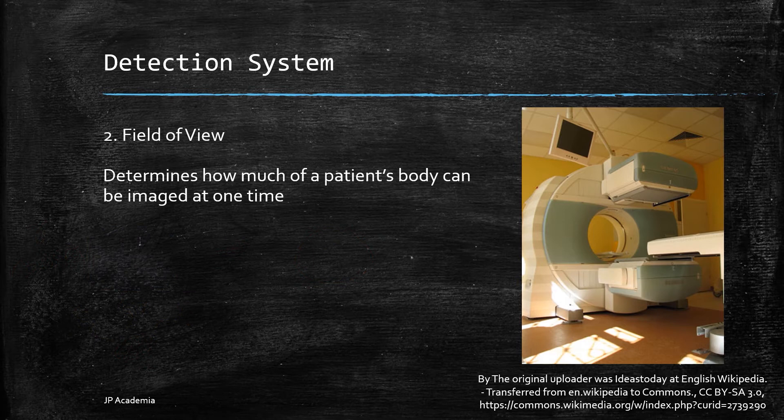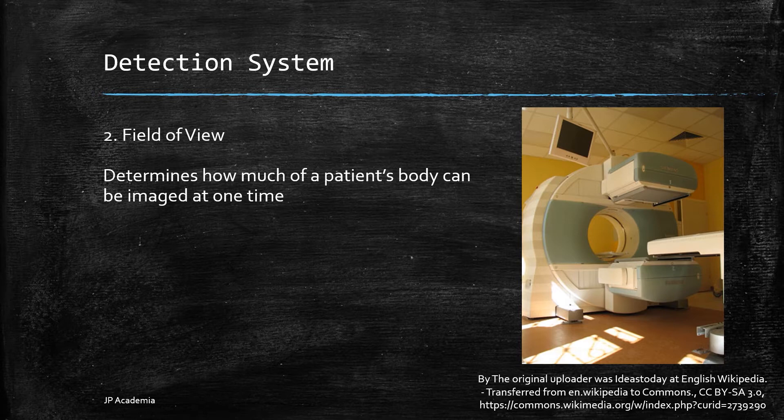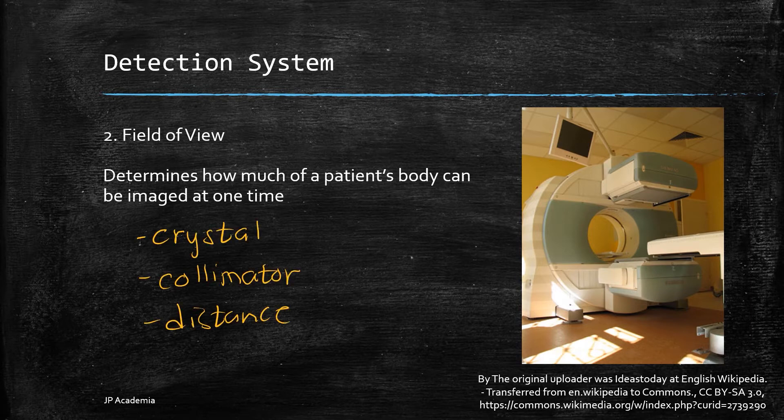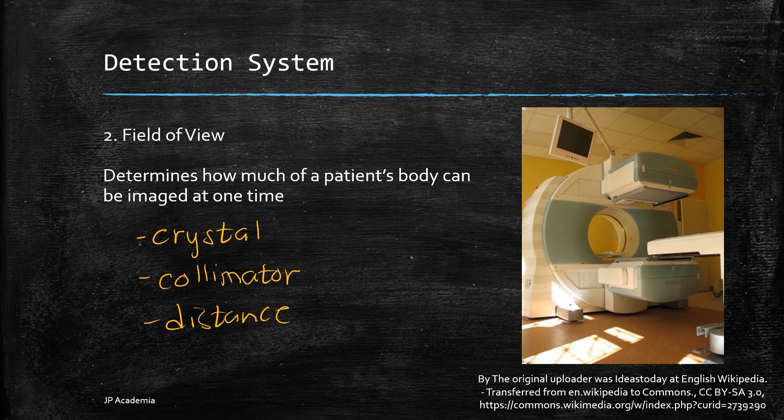Next, we have the field of view or FOV, and this determines how much of the patient's body can be imaged at any one time. The FOV depends on the crystal size, the collimator type, and the distance between the object being imaged and the camera crystals.